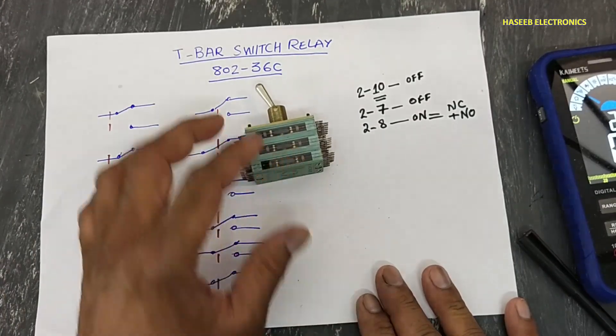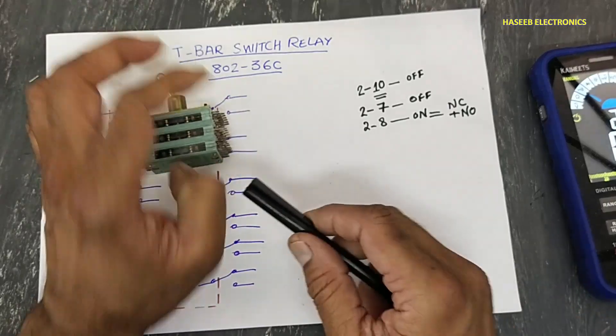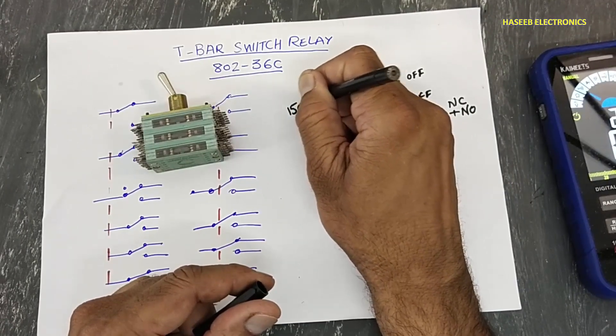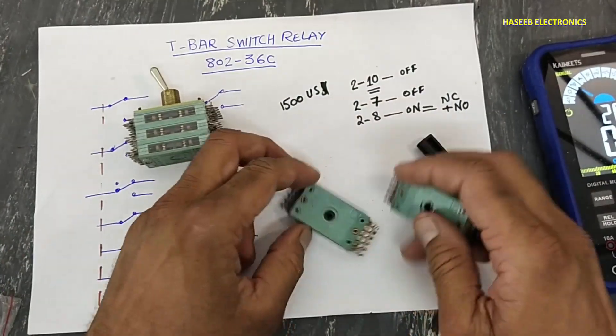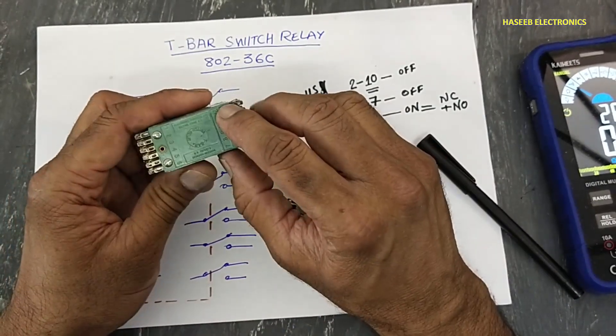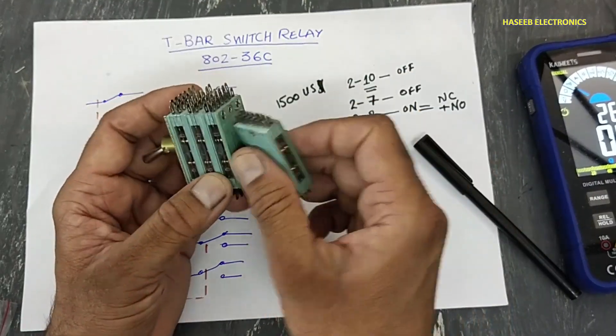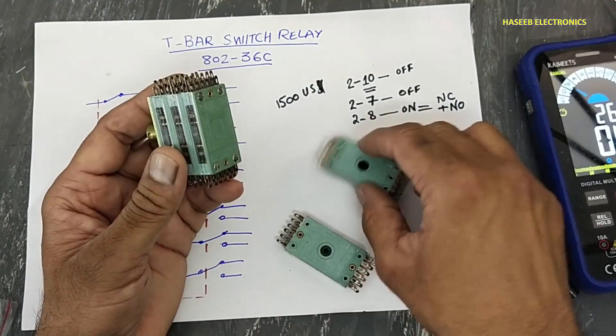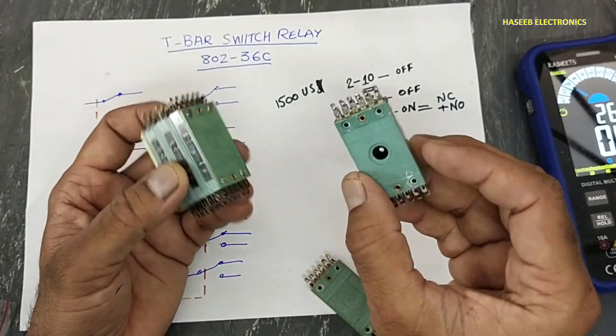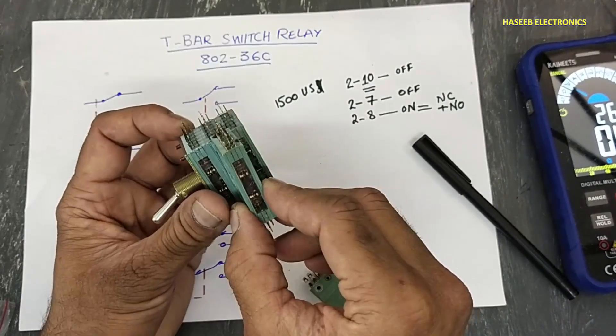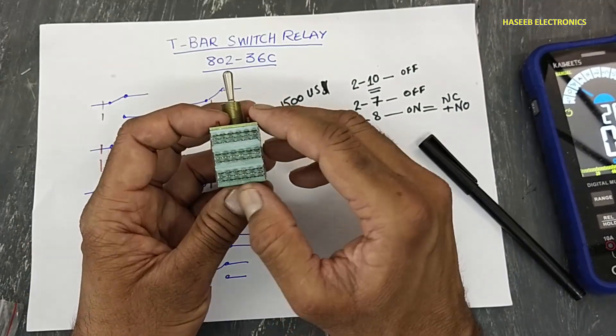First, we can replace the complete switch, but its price is approximately 1,500 US dollars, which is very high. If we have spare contact sets, we can remove these four screws — every section is separate — and just remove that stage and install a new one in its place. This is the second solution.